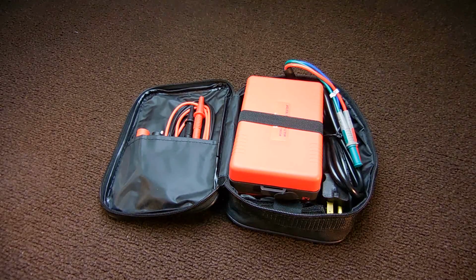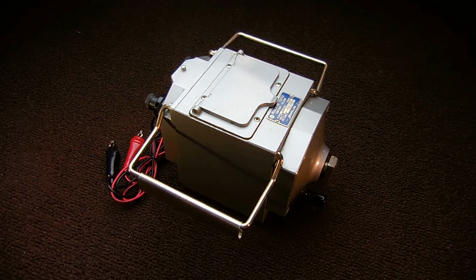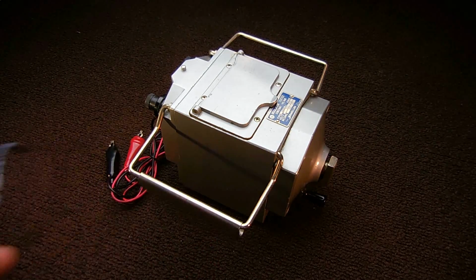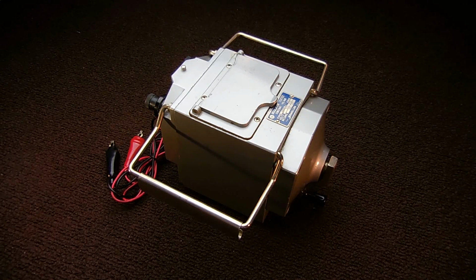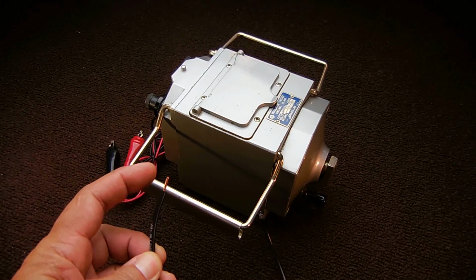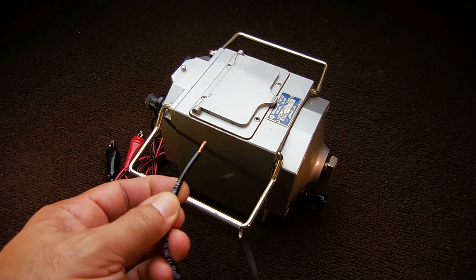Let's get started first with the crank Megger. First, I'd like to discuss how a Megger works and why it's different than an ordinary ohm meter. Meggers, or insulation testers, are designed to measure the resistance between a wire and the insulation of that wire. It can be insulation on a wire like you see here, or it can be enamel wire, which is used inside motors, relays, and transformers. You want to make sure the resistance is as high as possible between the center conductor and the outside of the insulation. Some of you may say, why not just use an ohm meter like you see right here?